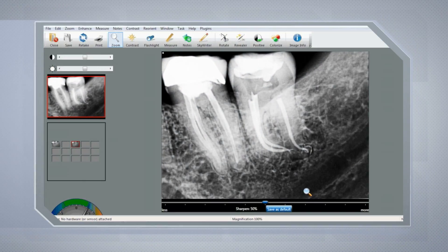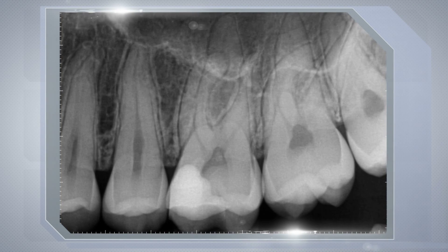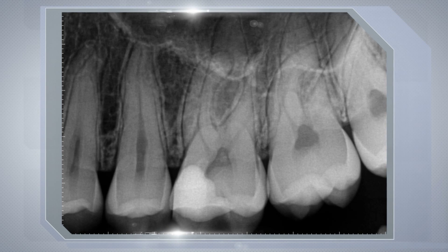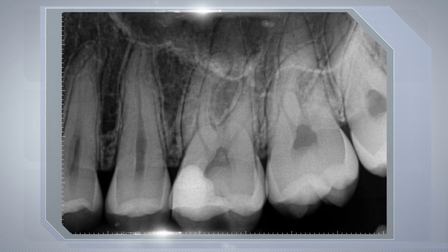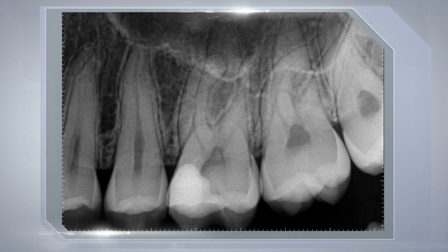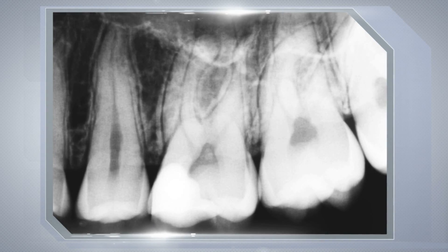In addition, multiple image settings are available to suit unique needs: general dentistry, with balanced image appearance; endodontic, with high contrast imaging to assist in diagnosis in the apical region; periodontic, with low contrast imaging to emphasize bone density and soft tissue; and restorative, with the highest contrast setting to focus on lesions in enamel and dentin.